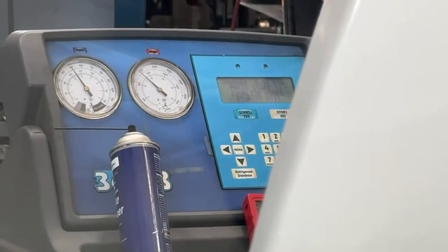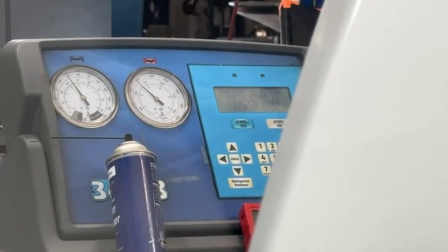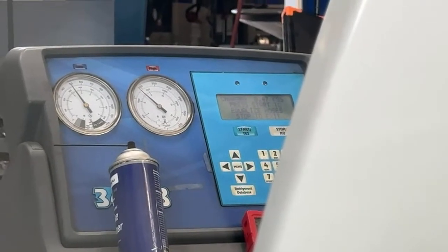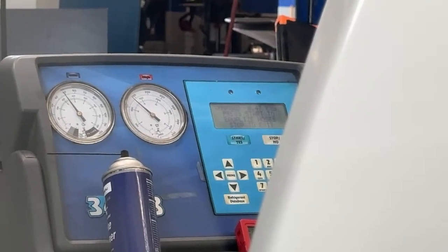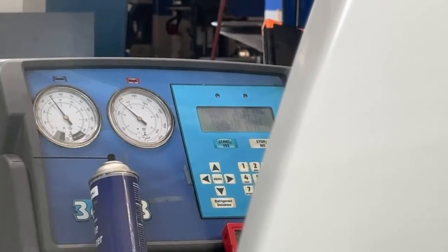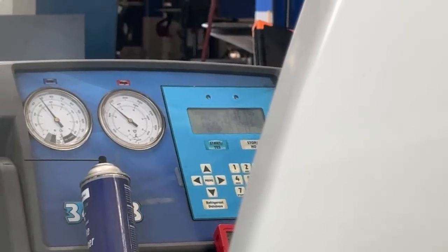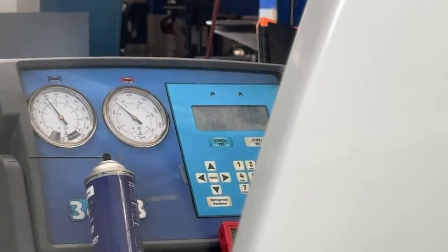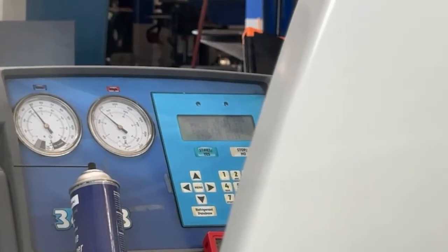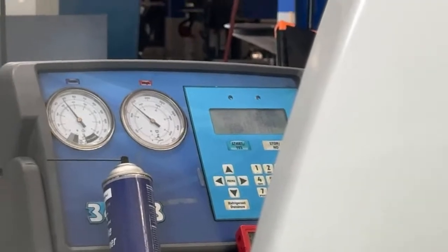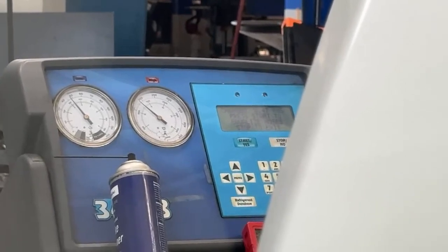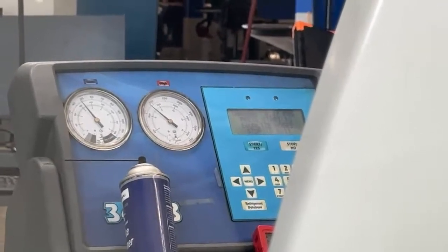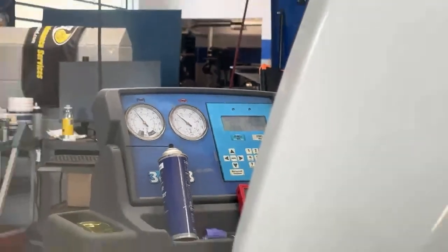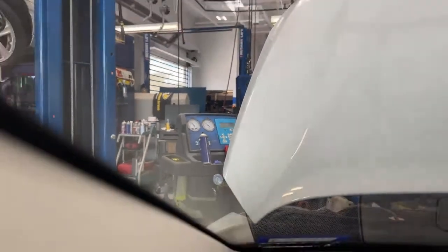Why we're not getting a good enough low side, why the pressure on the low side is too high, well, that's just going to mean that the compressor is not sucking in enough efficiently. It might have bad vanes now because I did see some metal in the system. So this compressor could have kamikazed itself running on a low charge because the previous shop reused O-rings.